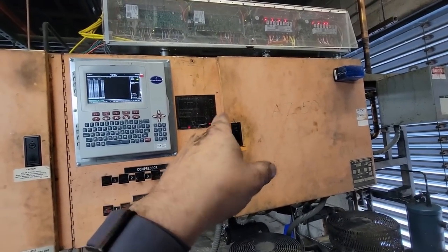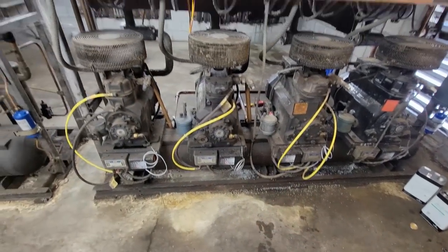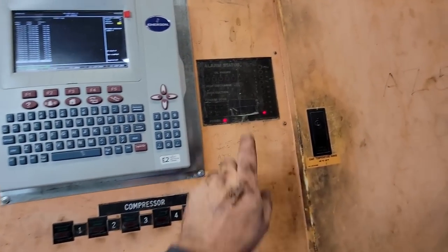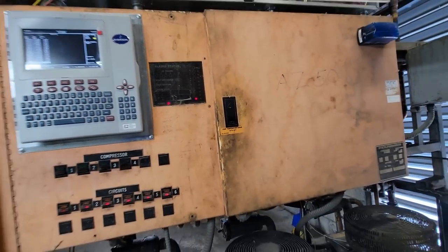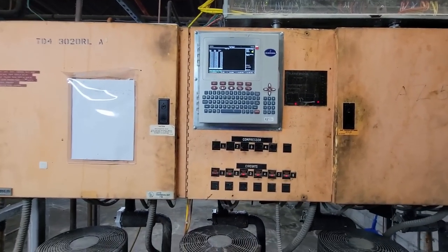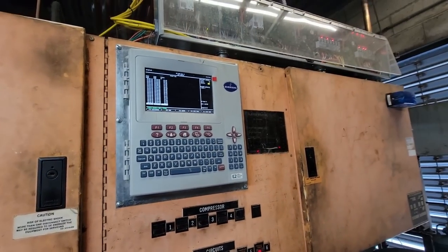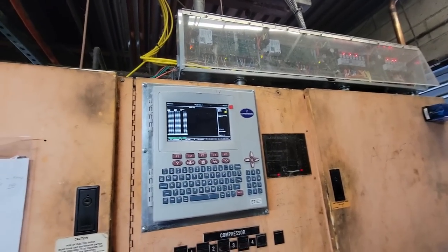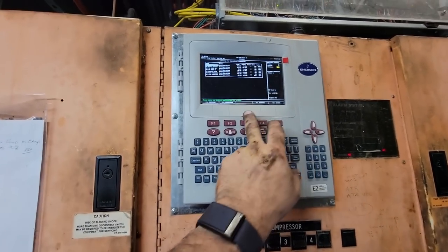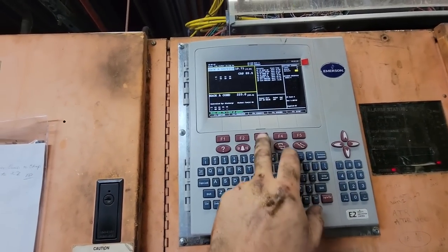Couldn't tell remotely how much refrigerant's in there. They don't have that sensor on here. This is an old control system that was actually not even Comtrol. I forget who, a Kysor Warren old-fashioned thing there. I mean, some of these stores I've got are just really antiquated. So this stuff here was just redone in the last year or two. And we just don't have all the goodies on it.